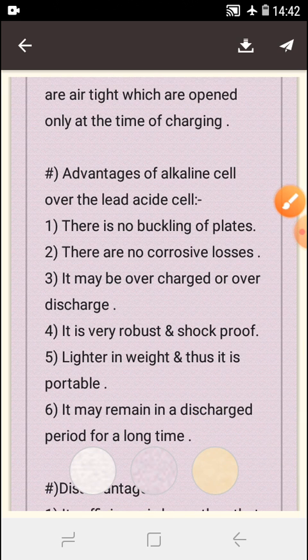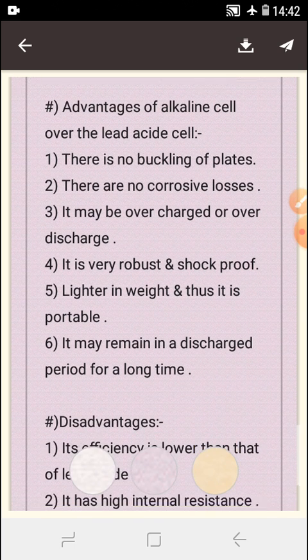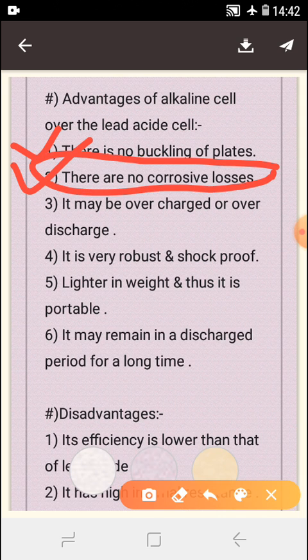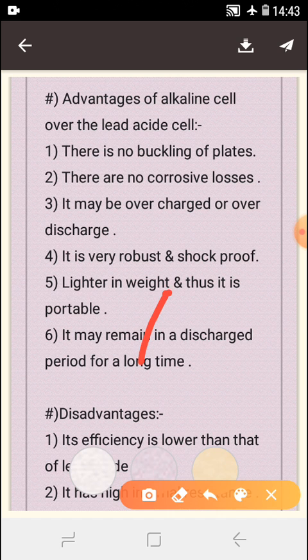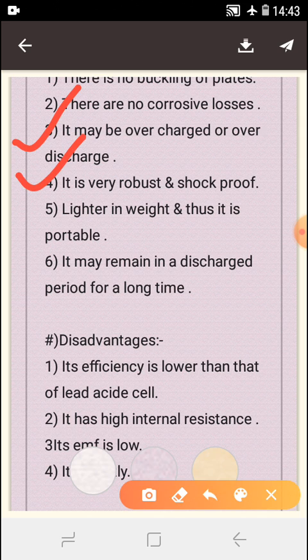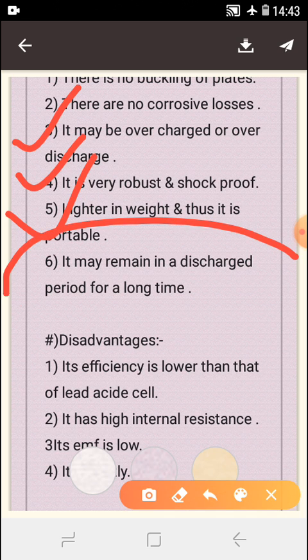Advantages of alkaline cell: Number one, there is no buckling of plates. Number two, there are no corrosion losses. Number three, it may be overcharged or over-discharged. Number four, it is very robust and shockproof. Number five, it is lighter in weight and thus portable. Number six, it may remain in a discharged condition for a long time.